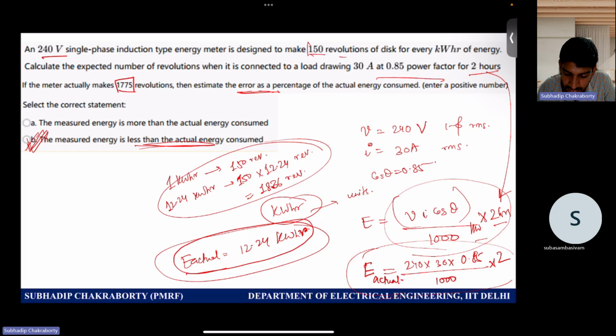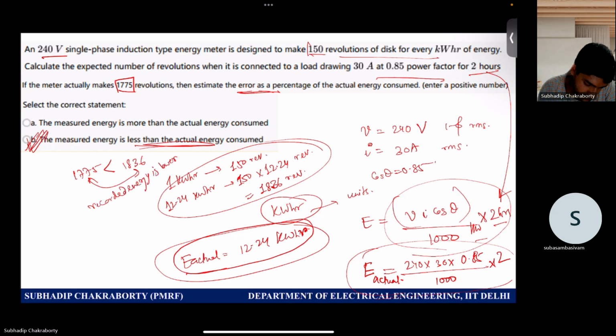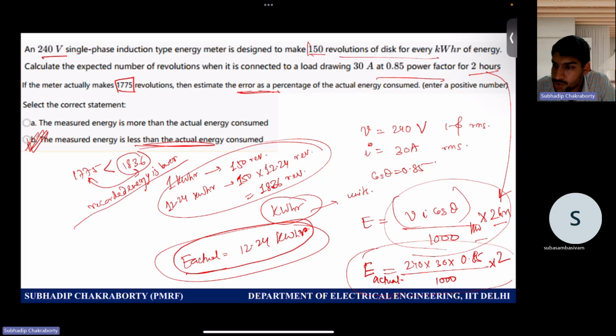Because for 150 revolutions you have 1 kilowatt hour, if it is rotating lower than 1836 — 1775 is less than 1836 — so obviously the recorded energy is lower. Because for the true energy to be recorded, it would have rotated 1836 times, but it rotated 1775 times as per the problem. So the energy recorded will be lower than the actual energy dissipated.